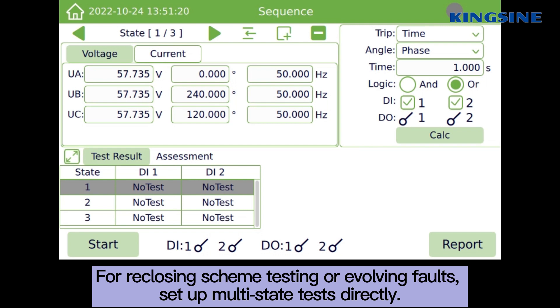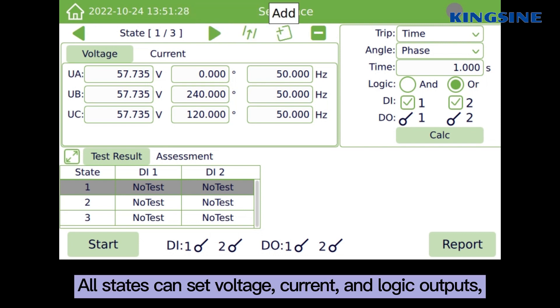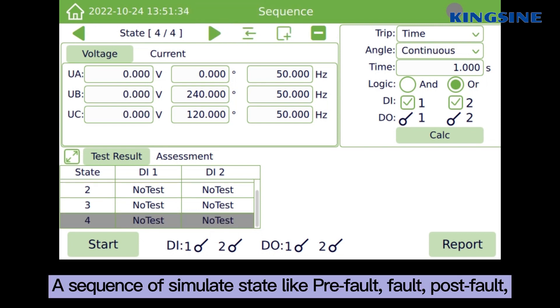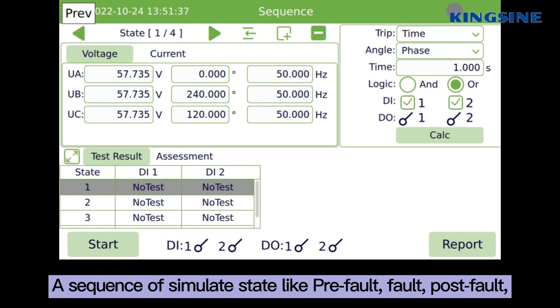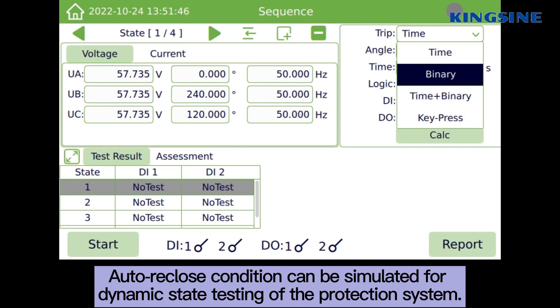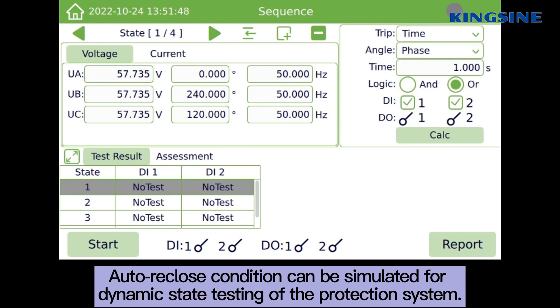For reclosing scheme testing or evolving faults, set up multi-state data tests directly. All states can set voltage, current, and logic outputs in a sequence of simulated states like pre-fault, fault, and post-fault. Auto-reclose conditions can be simulated for dynamic state testing of the protection system.